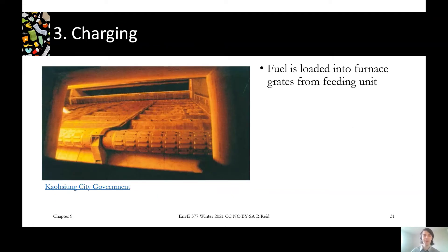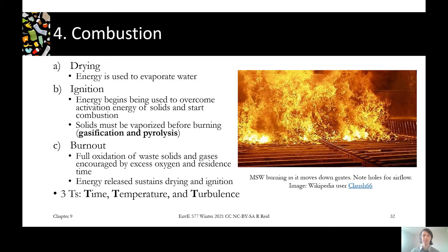The next stage is charging. A big grapple lifts the material and loads it into the front end of the furnace, where it's moved through the reaction on a system of moving grates. There are holes in the grates where aeration is supplied. As the waste moves through, the first thing that happens is drying — it needs to burn off moisture before it can start volatilizing and burning the solids. Once dried enough, it's able to ignite and the reactions we saw in the candle flame analogy begin.